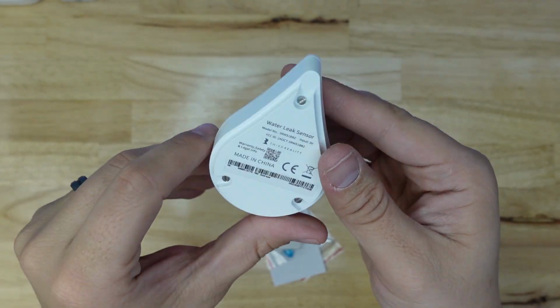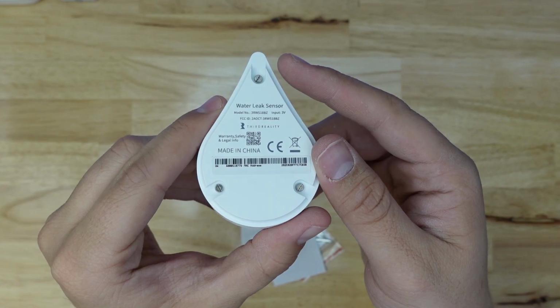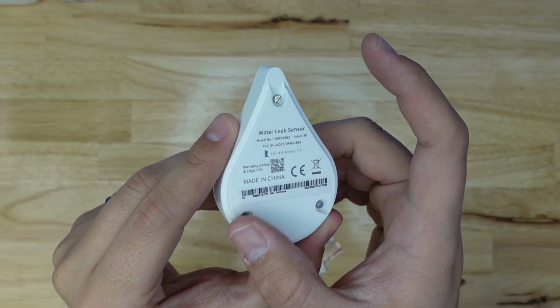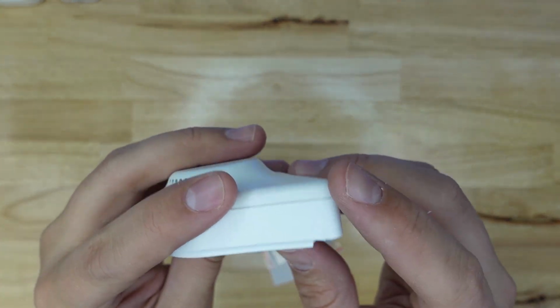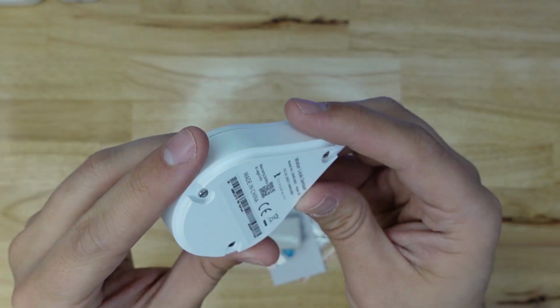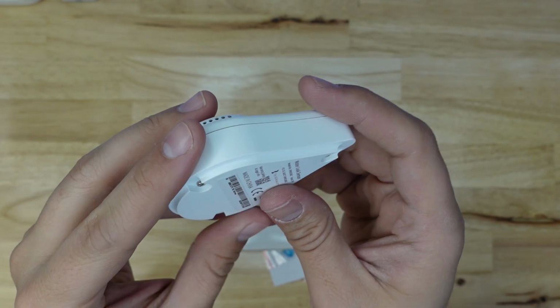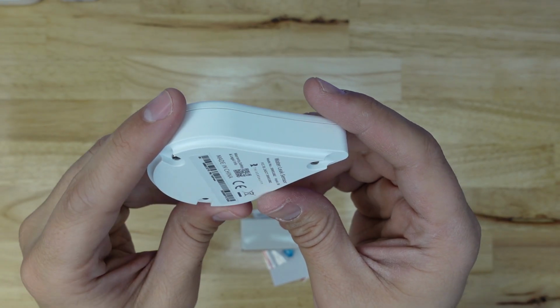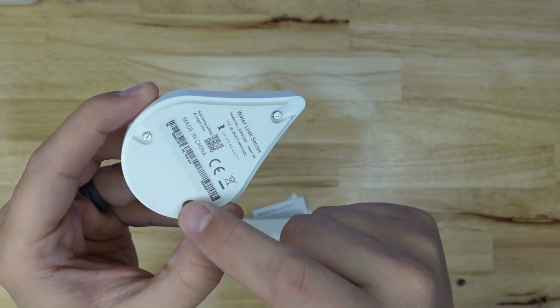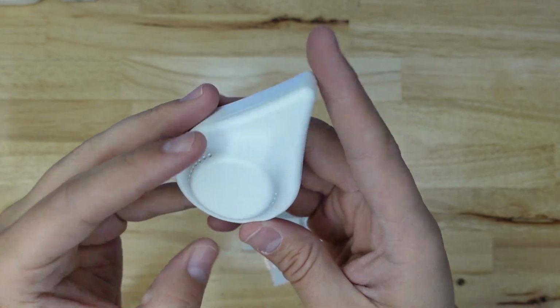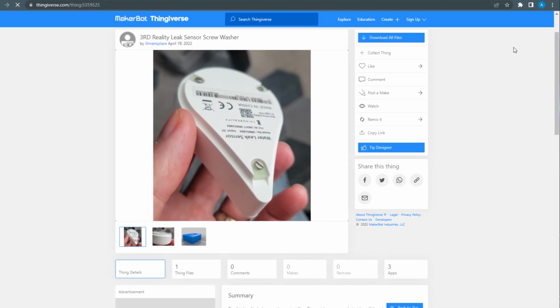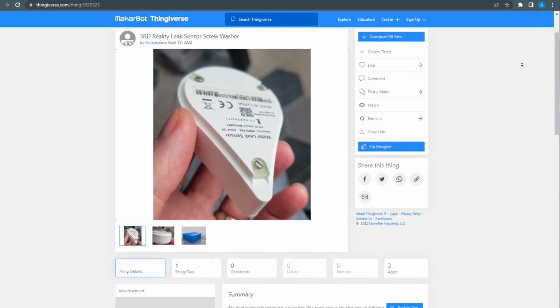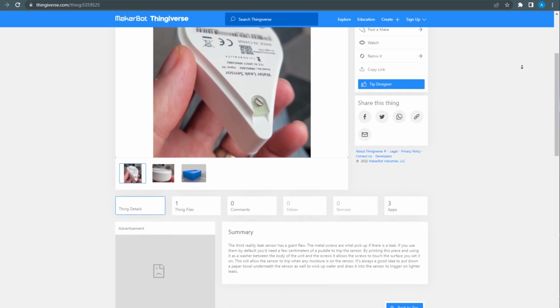On the bottom, you can see 3 flathead screws that act as electrodes for sensing leaks. If any two of them come in contact with water or other conductive surface, the leak alarm is triggered. You'll notice that the screw holes for these screws are recessed quite a bit, meaning that the screw heads are raised up a bit from the flat bottom of the sensor. This means that more water would need to accumulate to trigger the leak alarm compared to the other ones that we've looked at so far in this video. If you'd like to make it a little more sensitive, you can add some spacers underneath those screws in order to make them closer to the surface or sticking out below the surface and make it more sensitive.